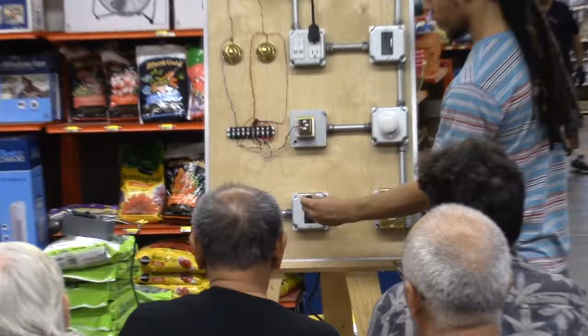Here is one of the old testers. If you want to test those two outlets again with the contact tester, you'll notice one side will light up and one won't, telling you which side of that outlet is hot and which is the neutral. And it chirps. You're right. Oh, that's fine, so you don't have to rely on visual. Correct - it'll light and chirp, and they'll all do about the same thing.